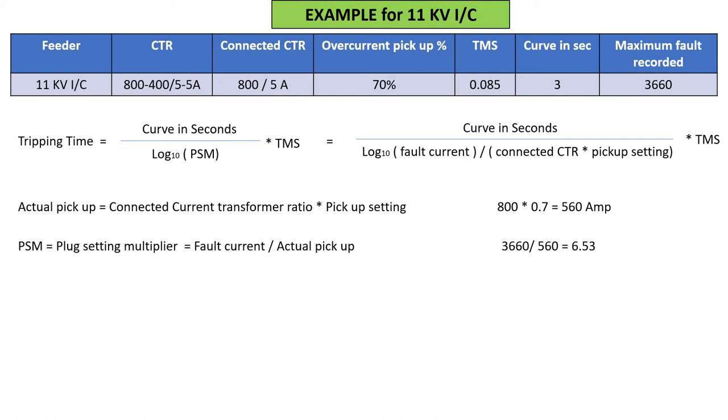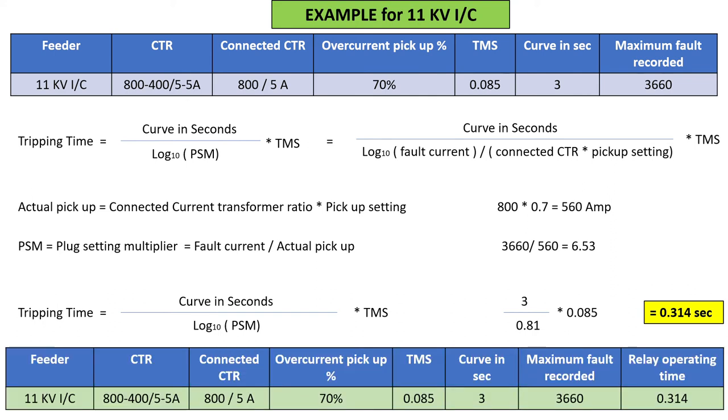Now PSM: fault current is 3660 ampere and our pickup is 560 ampere, so PSM is 6.53. To find tripping time, we take log of PSM with base 10 - that is log of 6.53 with base 10. Please make sure it's log, not ln. Our value is 0.81. Tripping time equals curve selected (3 second very inverse) divided by 0.81, multiplied by TMS 0.085. So tripping time is 0.314 seconds. Please pause the video and do it yourself for practice.